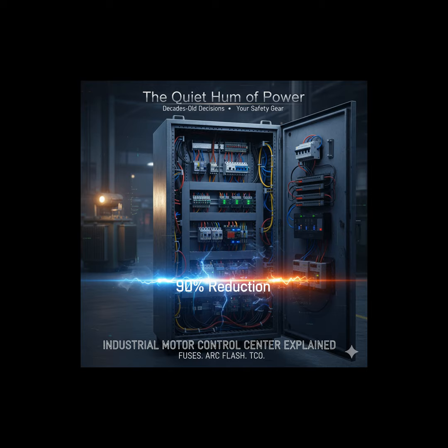And this leads us to a final, maybe provocative thought for you to consider. That initial design choice, fuses versus circuit breakers, isn't just a maintenance decision based on a ledger sheet. It's a foundational safety commitment that dictates the exposure level for every maintenance technician for the next 3 decades. Hmm. So when facilities undergo safety audits or upgrade their NFPA 70 compliance protocols, how often are they willing to reevaluate their entire installed protection scheme and invest in systems that fundamentally minimize the daily arc flash risk? That's something for you to explore within your own organization.